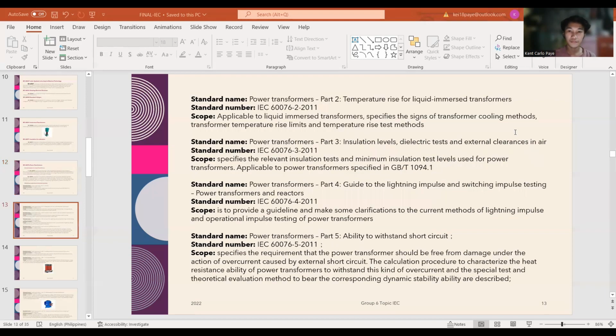Next is the temperature rise for liquid-immersed transformers. It is applicable to liquid-immersed transformers and specifies designs of transformer cooling methods, transformer temperature rise limits, and temperature rise test methods. This standard has been updated. It includes the following significant technical changes with respect to the previous edition. The winding hotspot temperature rise limits were introduced among the prescriptions. The procedure for the temperature rise test was improved in relation to the new thermal requirements. And also, five informative annexes were added in order to facilitate the implementation of this standard.